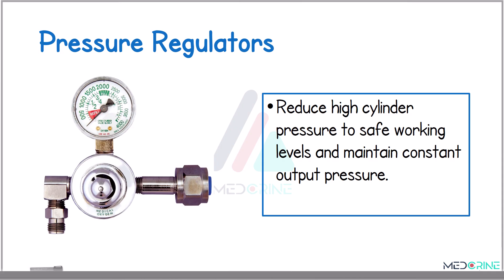Pressure regulators are used to reduce the high gas pressure from the cylinders to a safe and constant working pressure, and this protects downstream components and maintains a consistent flow of oxygen to the patient.